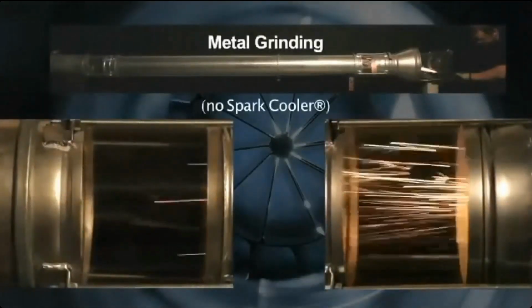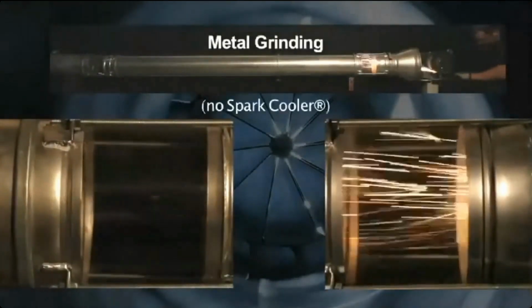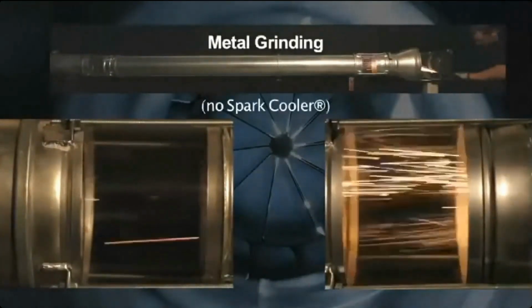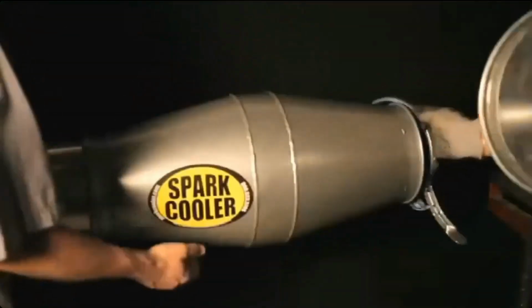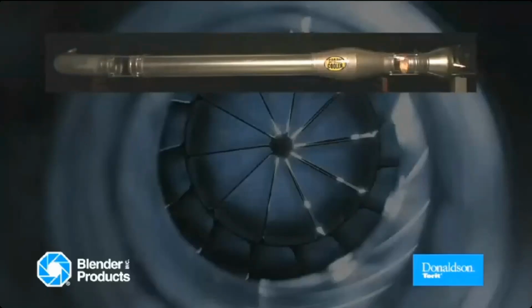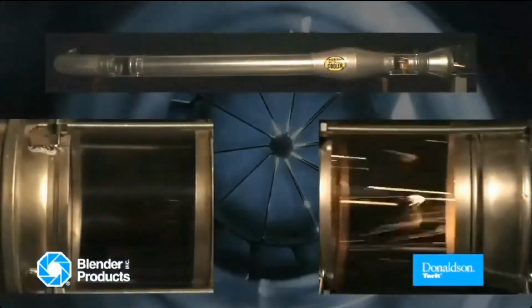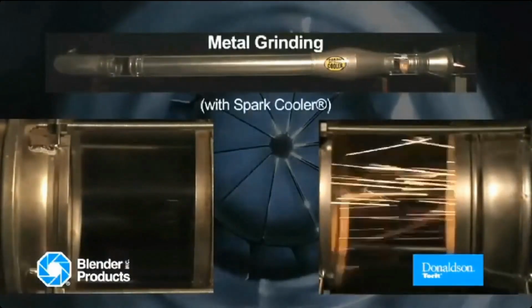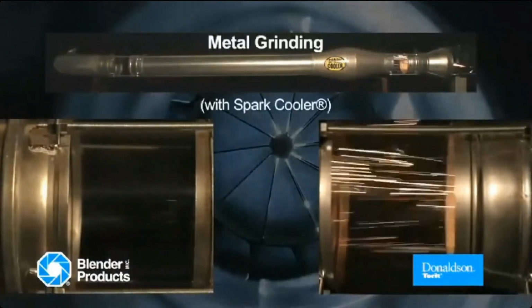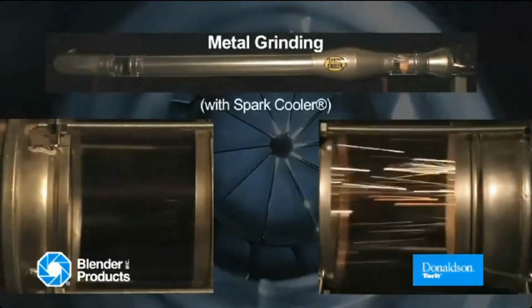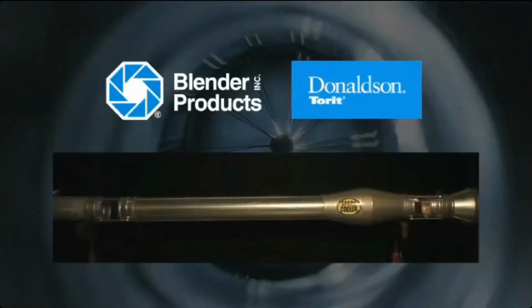All right, so essentially what you're seeing here is metal grinding application with no spark cooler. And then when we introduce the spark cooler to the system, you can see the application generating sparks going through the spark cooler, and then out the other side of the duct there are no sparks that are passing. So that just shows you the effectiveness of the spark cooler itself.